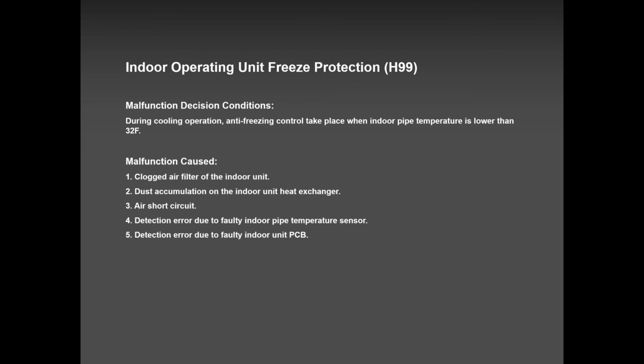Dry mode needs humidity. So if you are having humidity of 80% and above, dry mode is not bad. It will work fine. You will not have issues. And if you call me and say, Paul, humidity level is 80% and above, and the unit still shut down on H99, I strongly advise you to check your refrigerant. You are definitely low on refrigerant.